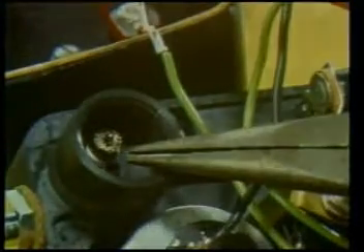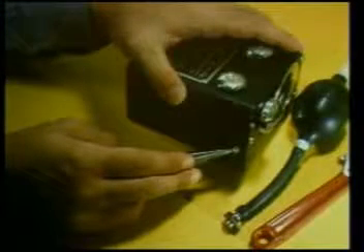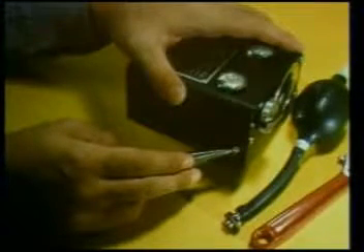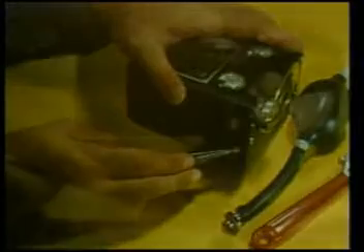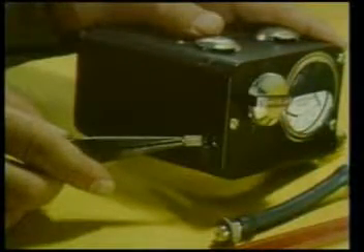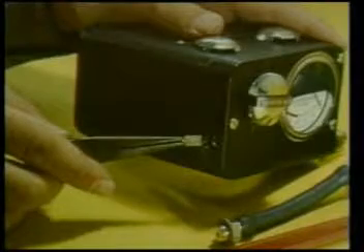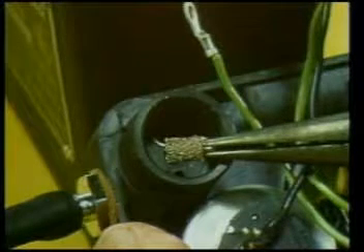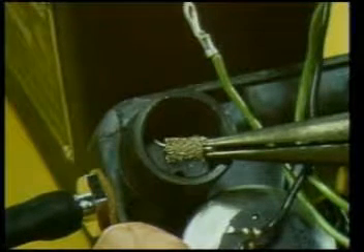To expose the inlet flashback arrestor, remove the detector filament and baffle plate. To expose the outlet flashback arrestor, remove the aspirator bulb coupling. Using long nose pliers, pull the cotter pin on which the arrestor is mounted. This may be difficult if excessive moisture in the sampling system has corroded the screen. Be sure the replacement arrestors fit snugly before reassembling the instrument.